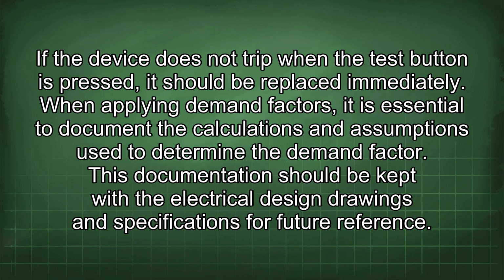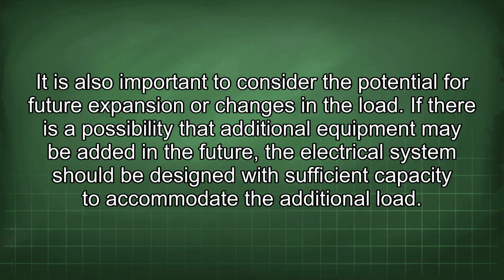When applying demand factors, it is essential to document the calculations and assumptions used to determine the demand factor. This documentation should be kept with the electrical design drawings and specifications for future reference. It is also important to consider the potential for future expansion or changes in the load. If there is a possibility that additional equipment may be added in the future, the electrical system should be designed with sufficient capacity to accommodate the additional load.